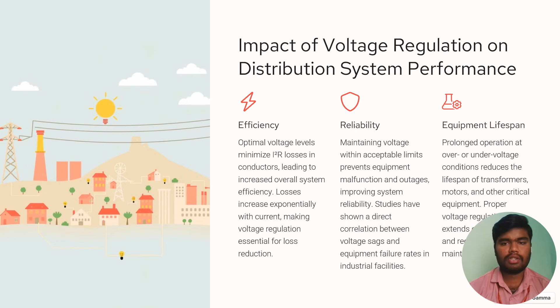Let's see how load variation affects voltage levels. Increased loads: higher current draw results in larger voltage drops along the distribution feeder, potentially causing undervoltage conditions for customers located further from the substation. In the second one, decreased load: reduced current draw can lead to voltage rise, particularly in systems with capacitor banks and distributed generation. This can result in overvoltage conditions and equipment damage.